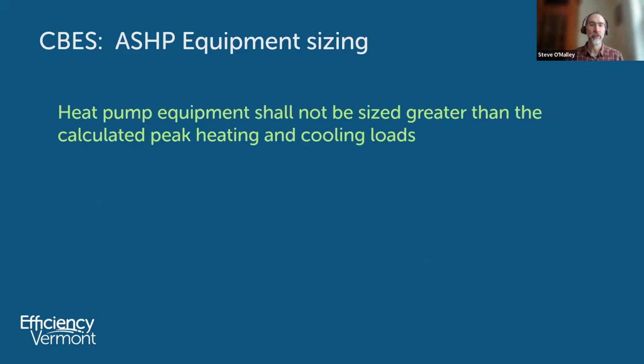CBES has a little section that talks about air source heat pump equipment sizing, and this is new for the 2024. It says heat pump equipment shall not be sized greater than the calculated peak heating and cooling loads. And this stems from the fact that we've learned, painfully so in many applications, that these air source heat pumps are significantly less efficient when oversized. They will short cycle, they'll come on, shut off, come on, shut off. And that absolutely destroys their efficiency, as well as being really hard mechanically on them. So code is making a point to say these things need to be sized appropriately. Also, outdoor condensing units that are serving multiple indoor heat pump units shall be sized equal to or less than the total capacity of the indoor units. So again, trying to get away from that oversizing issue.